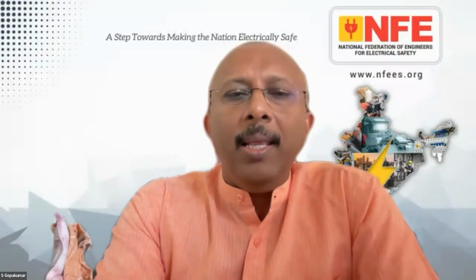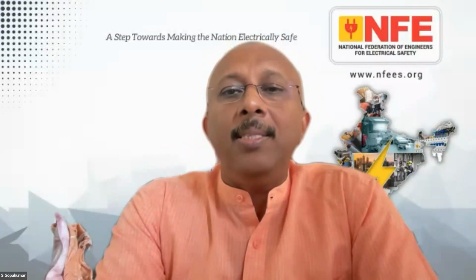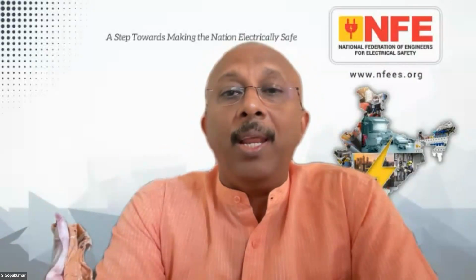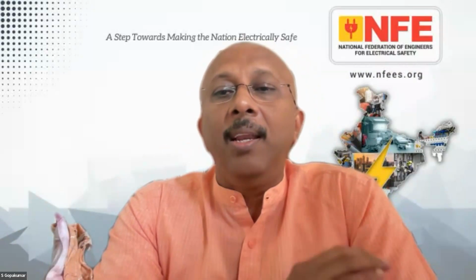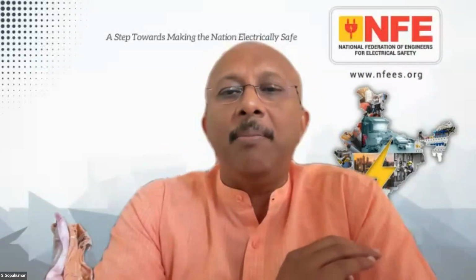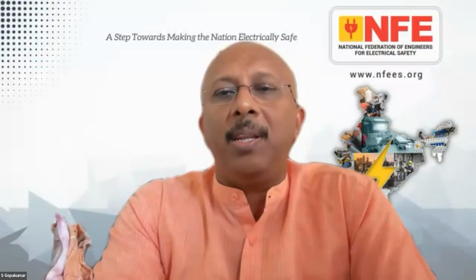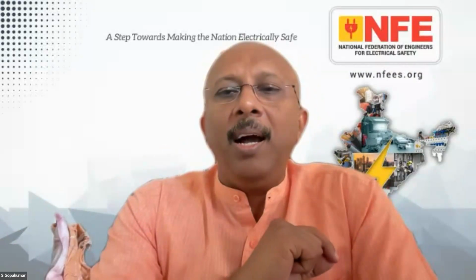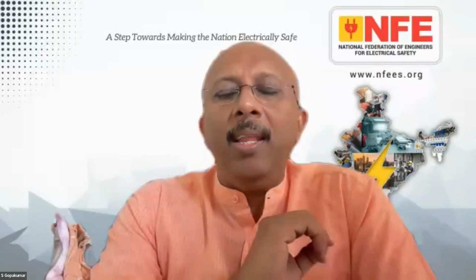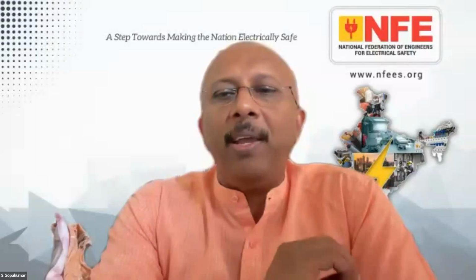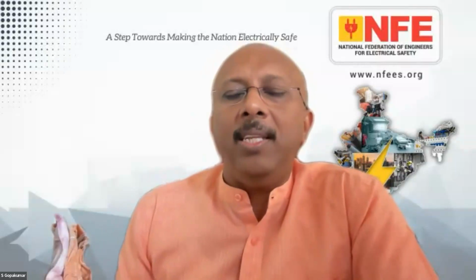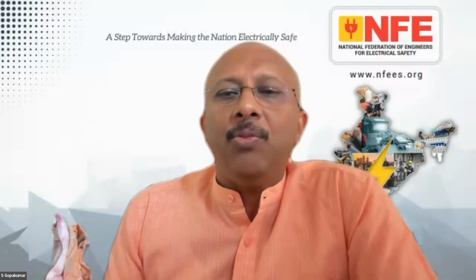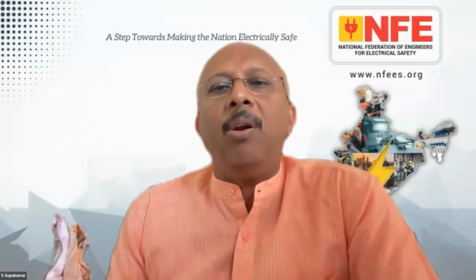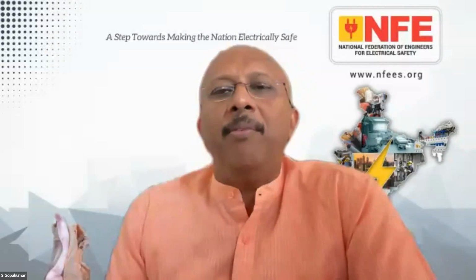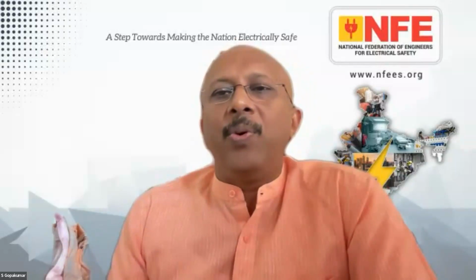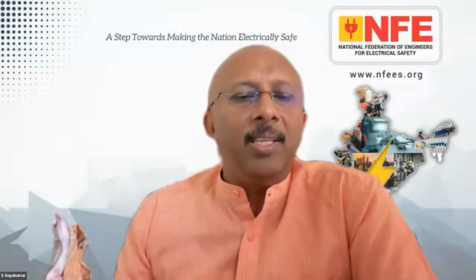Also, I would like to mention that this particular test is not new in our standards. IS 3043 of 1966, not now, 1966, has mentioned that this is the best test for earthing, with a picture. Similarly, IS 732 of 1989, Section 5, has a sequence and series of tests. Test number 8 is the fault loop impedance test. So these are already there in the documents. Unfortunately, we were not following them. Since the beginning of the standards, these were there.